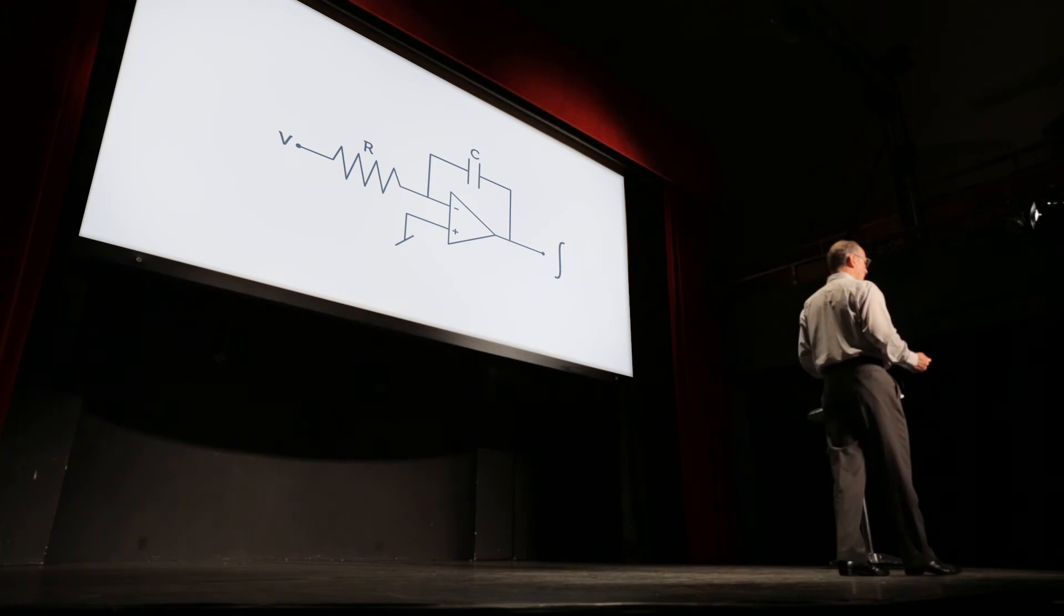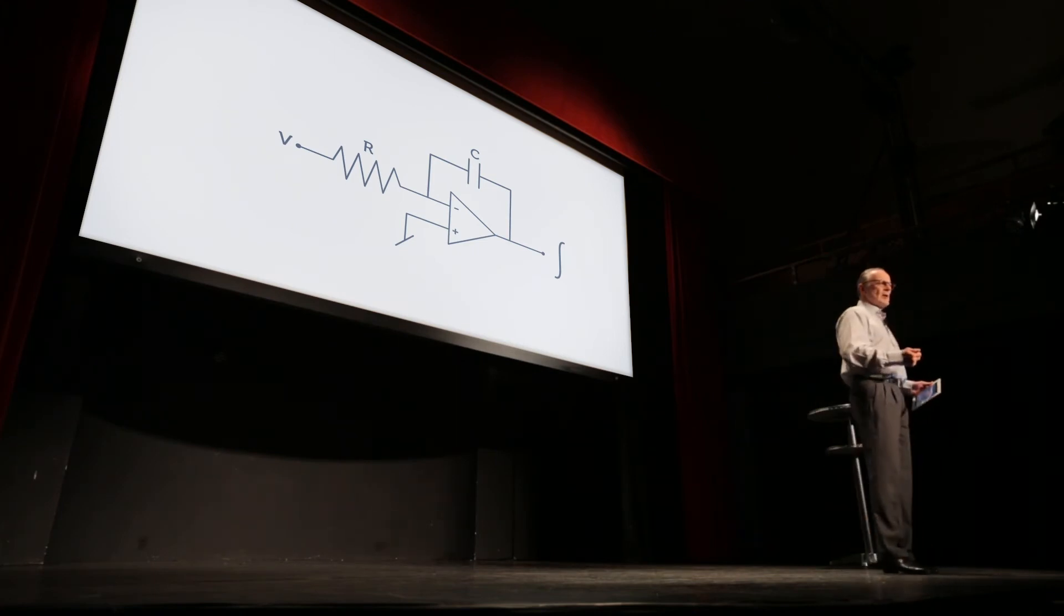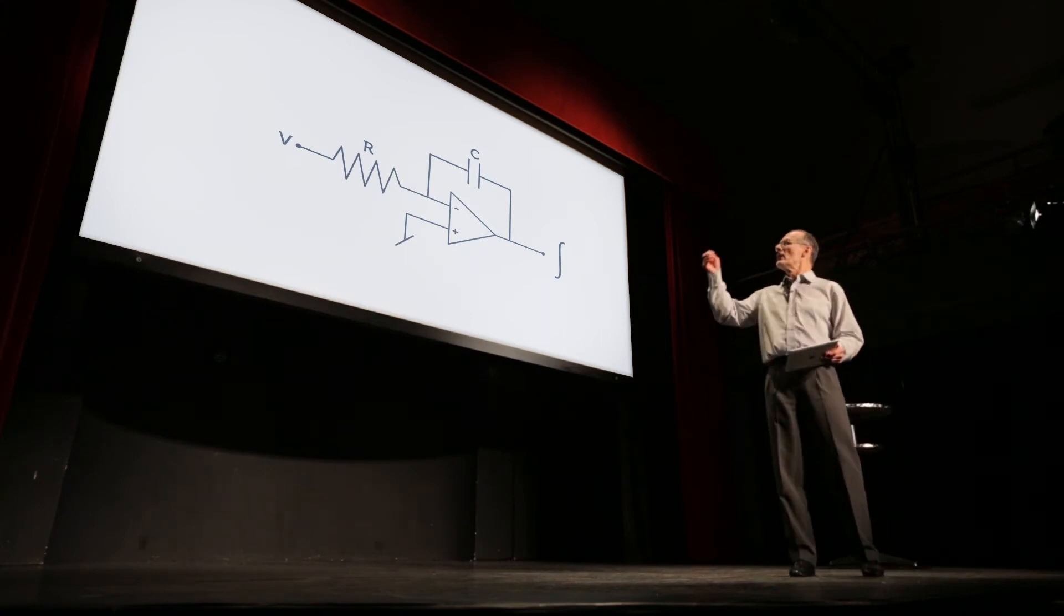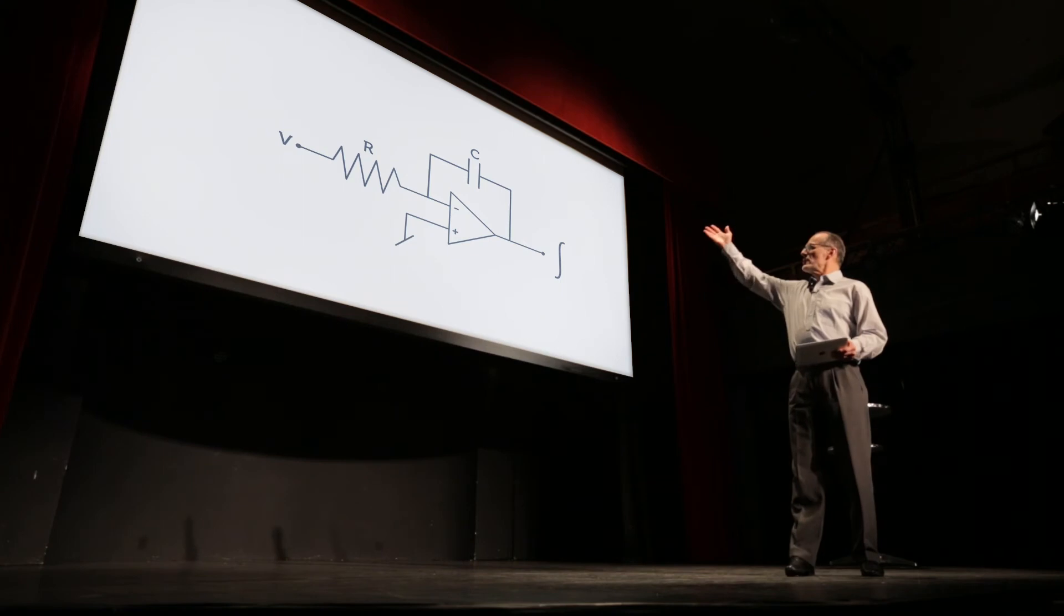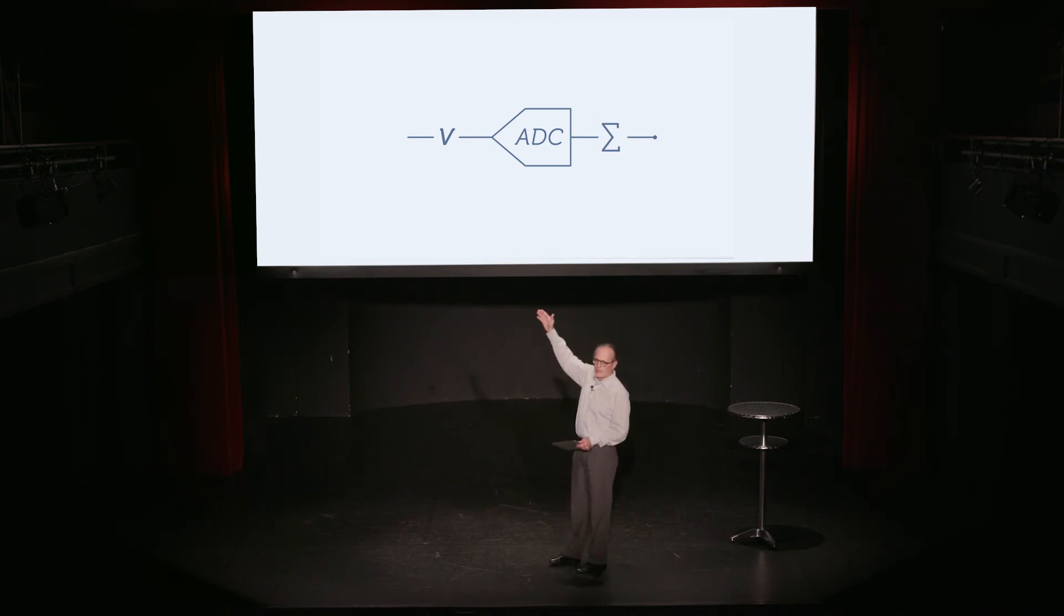So far, we've talked a lot about coils, but coils are just one half of a flux meter. The other half is the voltage integrator. So, usually, a voltage integrator is just a classic analog integrator as we see right here. But more and more, as the performance of ADCs improves, we can use digital integration where we convert or digitize the signal at the front end and then the integral just becomes a numerical sum. Both techniques have their advantages and their disadvantages.